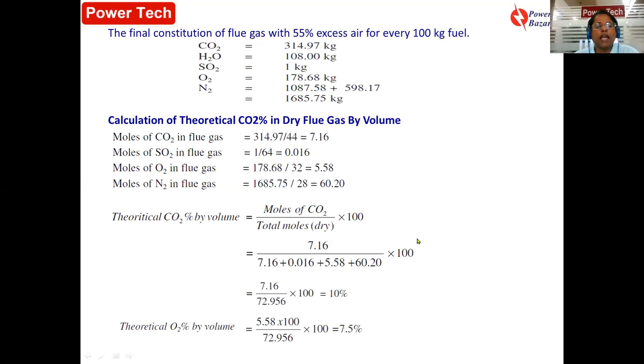So oxygen measurement or CO2 measurement in the dry flue gas is a tool to see what excess air percentage you are supplying, and whether you can minimize the excess air, so that you get good combustion and minimize the excess air supplied to the combustion process.